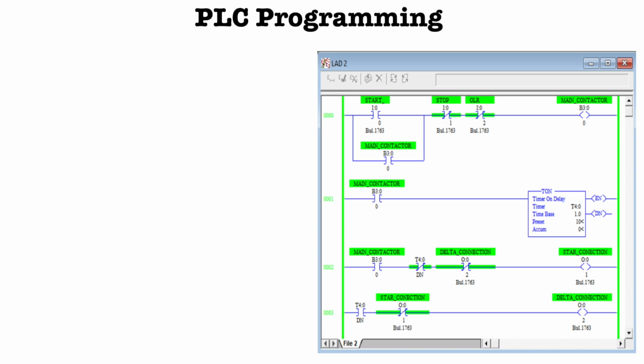As you can see in the diagram, in the first rung, the start switch is represented by I colon 0/0 and the stop switch is represented by I colon 0/1, and beside them the OLR, meaning overload relay, is represented by I colon 0/2. In the first rung, you can see the latching is also provided to the start switch with the main contactor, and in the second rung you can see the main contactor is connected to the TON timer. The address of the timer is represented by T4 colon 0. Time base is 1 second and we are using the preset value of 10 seconds.